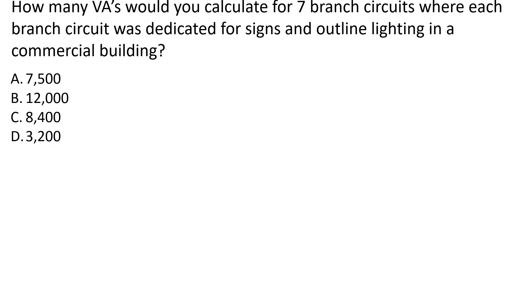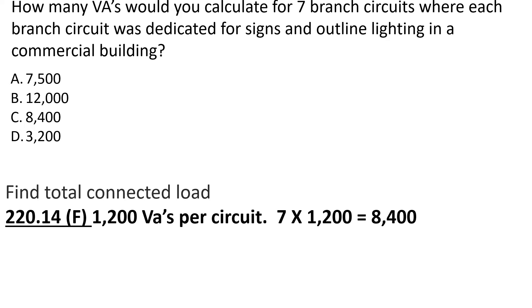How many VAs would you calculate for seven branch circuits where each branch circuit was dedicated for signs and outline lighting in a commercial building? Step one: find our total connected load. For this, we're going to go to 220.14F, and it lets us know that for each circuit it's going to be 1,200 VAs per circuit. We have seven circuits multiplied by 1,200, which equals 8,400 VAs.